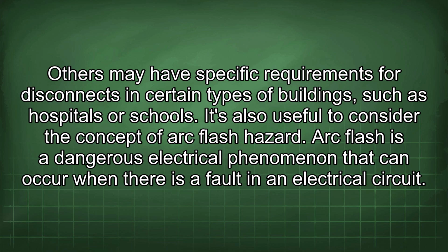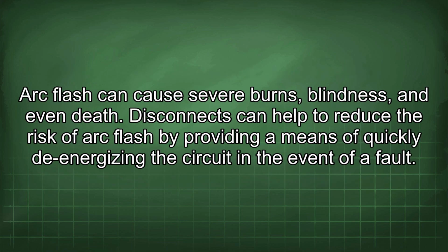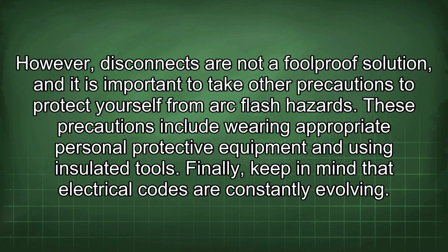It's also useful to consider the concept of arc flash hazard. Arc flash is a dangerous electrical phenomenon that can occur when there is a fault in an electrical circuit. Arc flash can cause severe burns, blindness, and even death. Disconnects can help to reduce the risk of arc flash by providing a means of quickly de-energizing the circuit in the event of a fault. However, disconnects are not a foolproof solution, and it is important to take other precautions to protect yourself from arc flash hazards. These precautions include wearing appropriate personal protective equipment and using insulated tools.